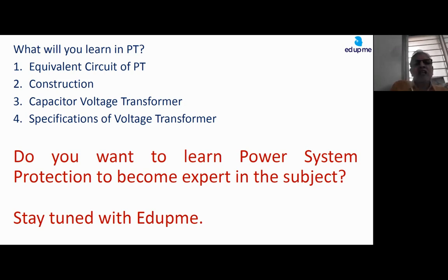And on the secondary, we connect through an auto transformer and a small auxiliary transformer of hardly 1 kVA, 230 by 40 volt or 230 by 15 volt. The 230 volt is controlled through a single phase auto transformer connected to 230 volt AC supply, the output of the auto transformer goes to an auxiliary transformer 230 by 15 volt, and then we connect a digital ammeter and digital voltmeter or digital multimeter for measuring the excitation current, IE, and the open circuit voltage, VOC.